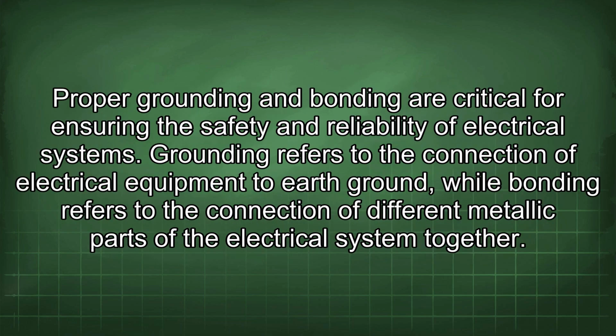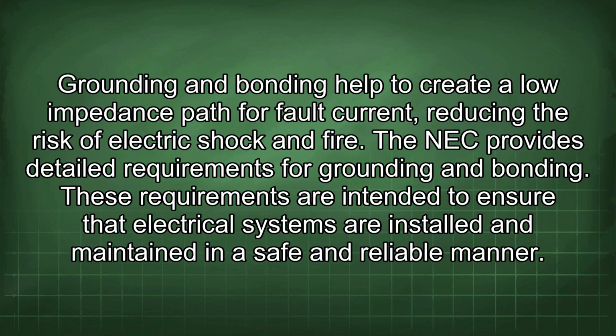Proper grounding and bonding are critical for ensuring the safety and reliability of electrical systems. Grounding refers to the connection of electrical equipment to earth ground, while bonding refers to the connection of different metallic parts of the electrical system together. Grounding and bonding help to create a low impedance path for fault current, reducing the risk of electric shock and fire. The NEC provides detailed requirements for grounding and bonding.